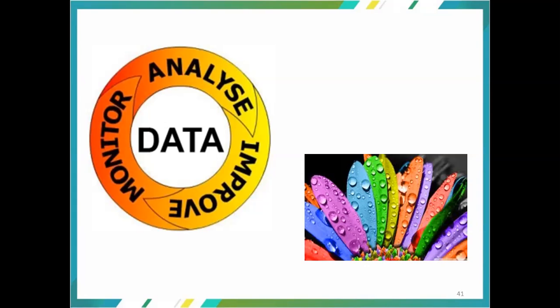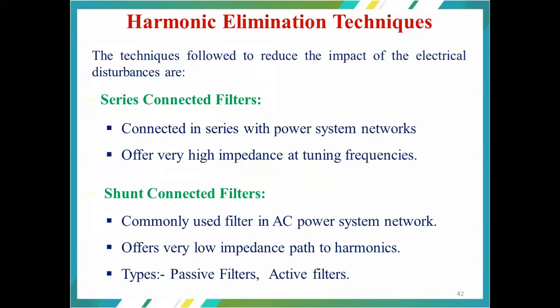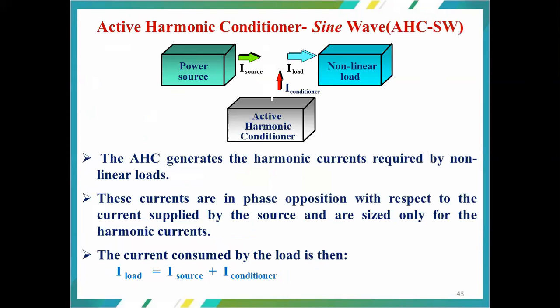Which is going to be at attractive prices also. The harmonic elimination technique, the filters we categorized into active, passive, and hybrid. When it comes to the connection, there are two possible ways: one is series connected, and the second one is shunt connected. And we can adopt the required type depending on the requirements and the location. So the active harmonic conditioner is going to be like this.